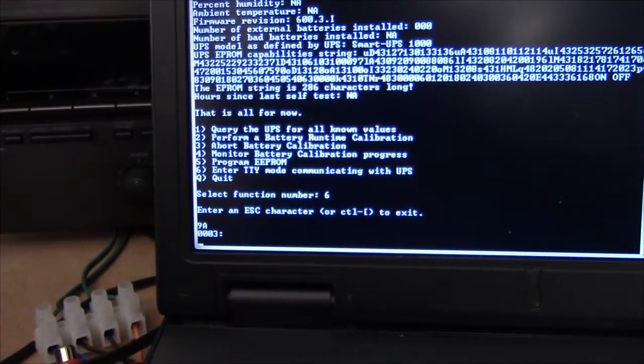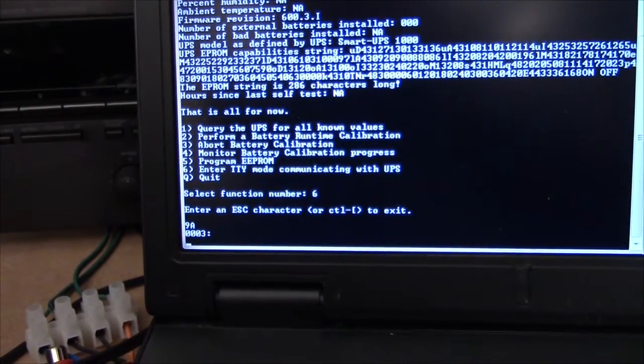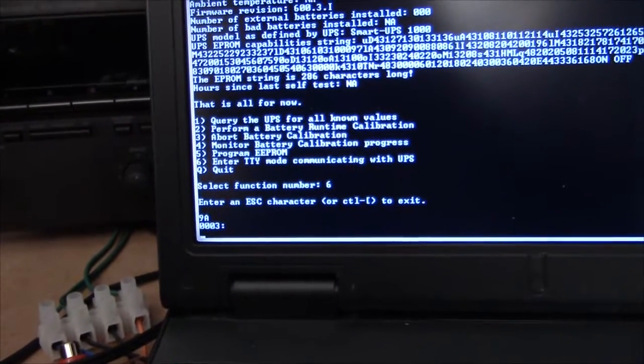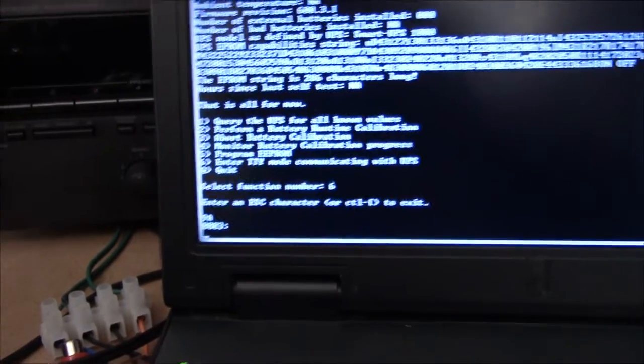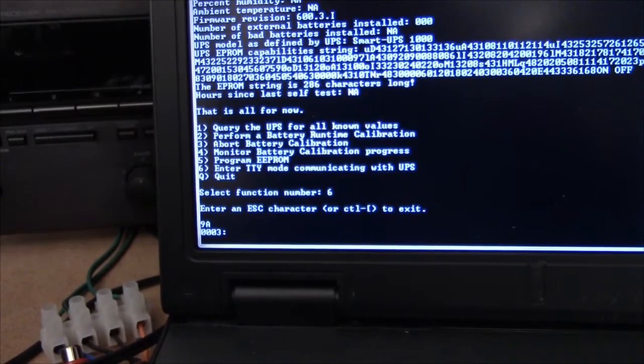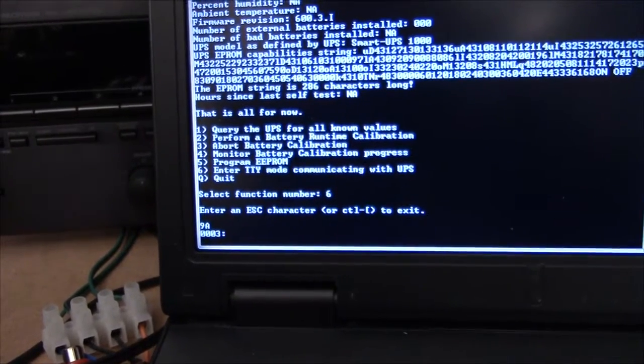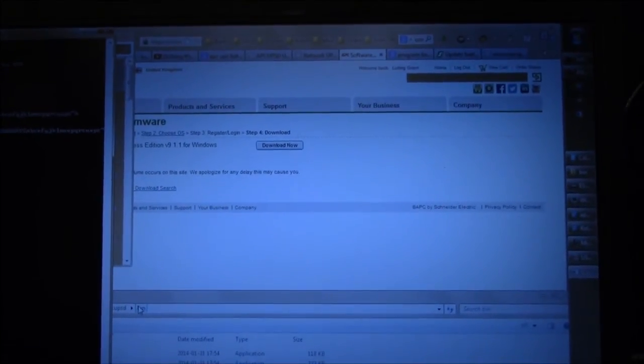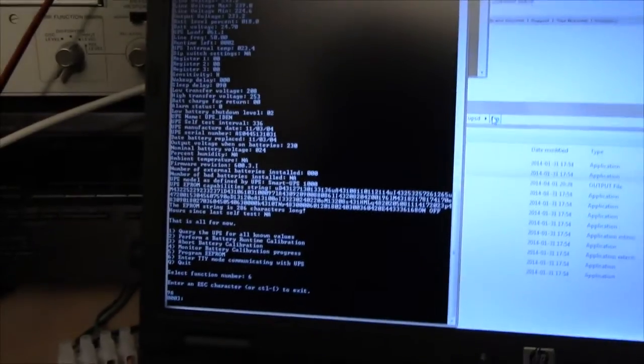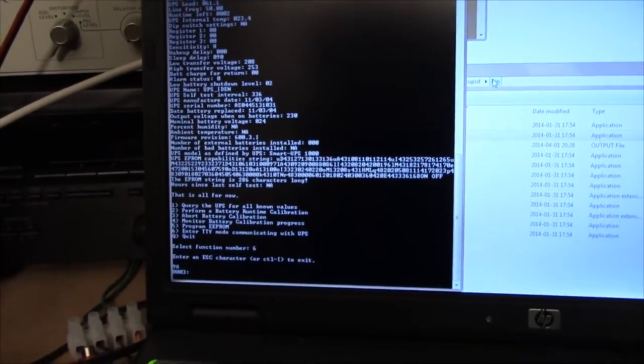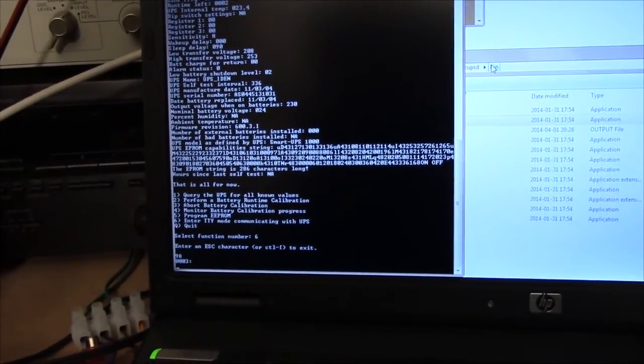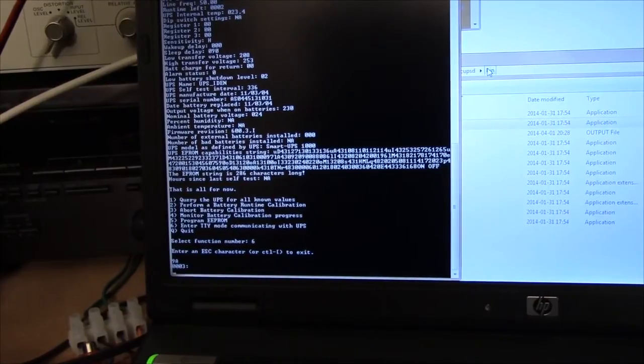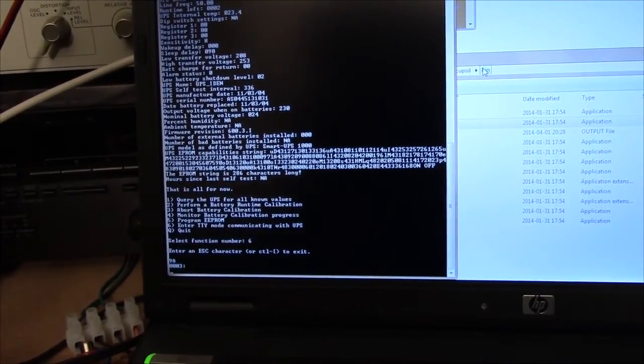So, it's adjusted itself to 9. So, I was fairly spot on when I set the new battery constant, which I did by just checking out the runtime chart on APC's site, and putting a constant load on the UPS, and adjusting until the UPS considers itself to run for the correct amount of time.